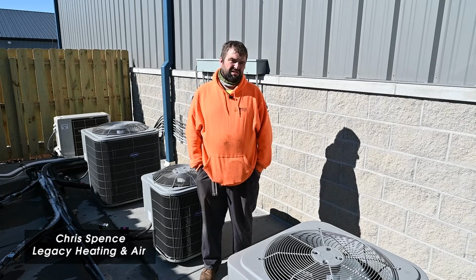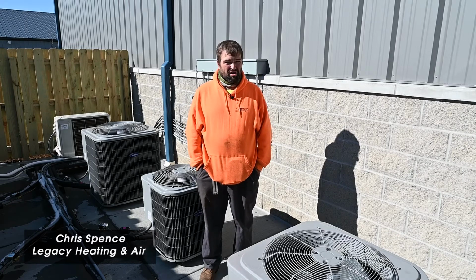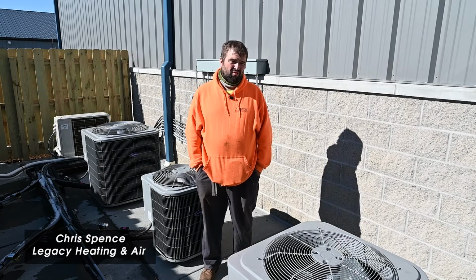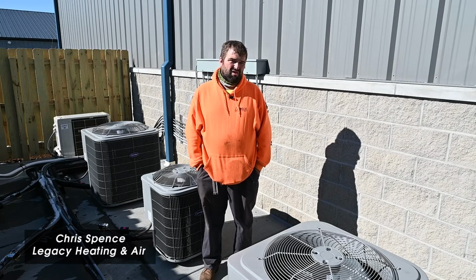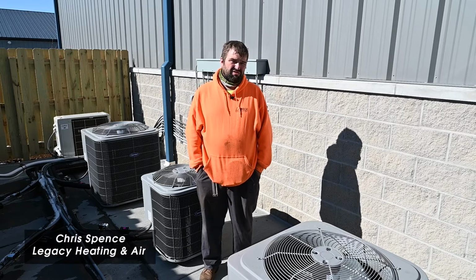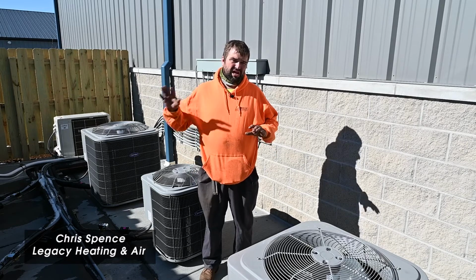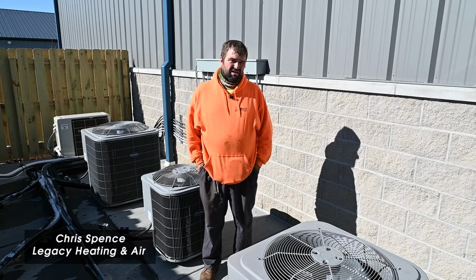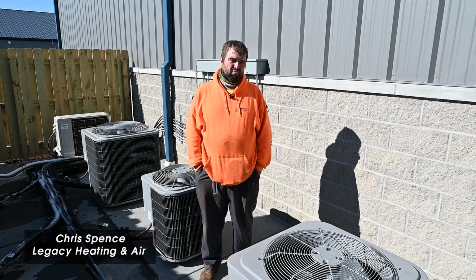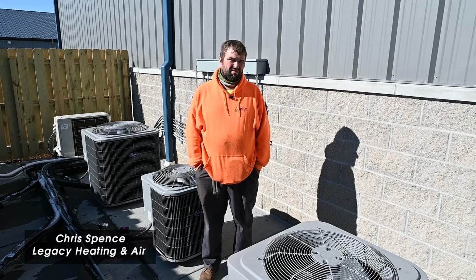You also have furnaces above the grid that have filters in them. The filters need to be changed at least once a month, because if they get clogged up, you won't get as good heat or cooling out. And the flame sensors need to be cleaned on them. The furnaces need to be cleaned at least every 6 months. We'll do the condensers one time, and then we'll come and do the furnaces one time. They do maintenance on them, so they'll run and operate perfectly, because you don't want to have any issues. You don't want to have people cold in the building while it's freezing outside. So preventive maintenance is an awesome thing to do.